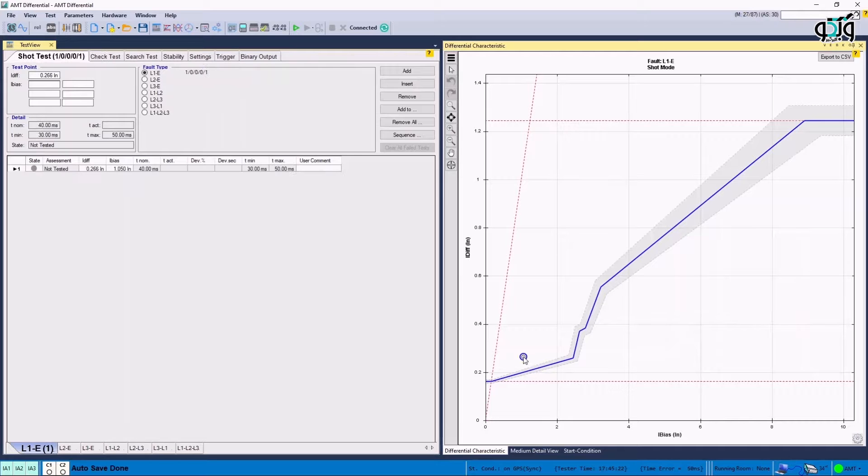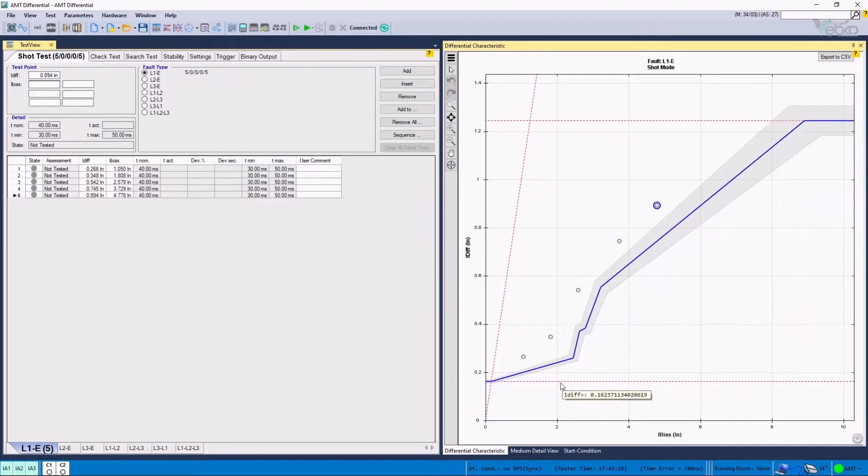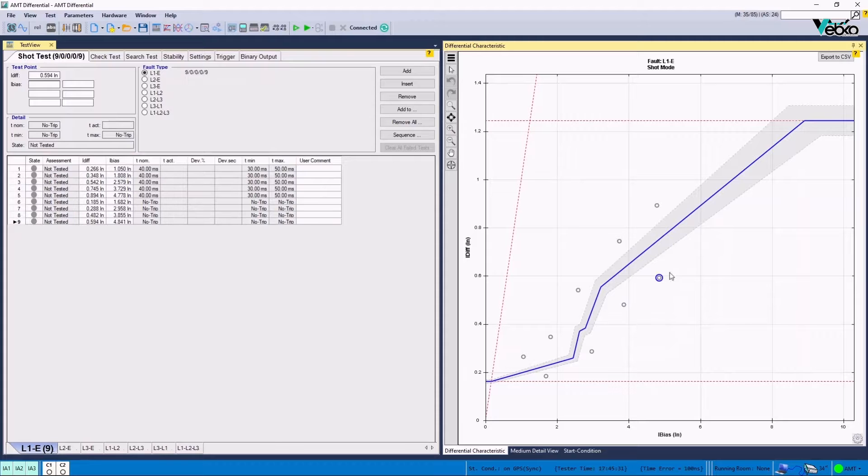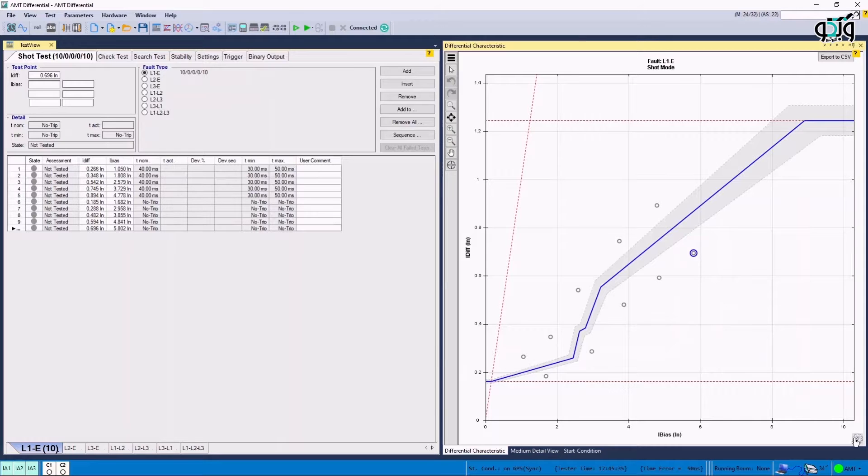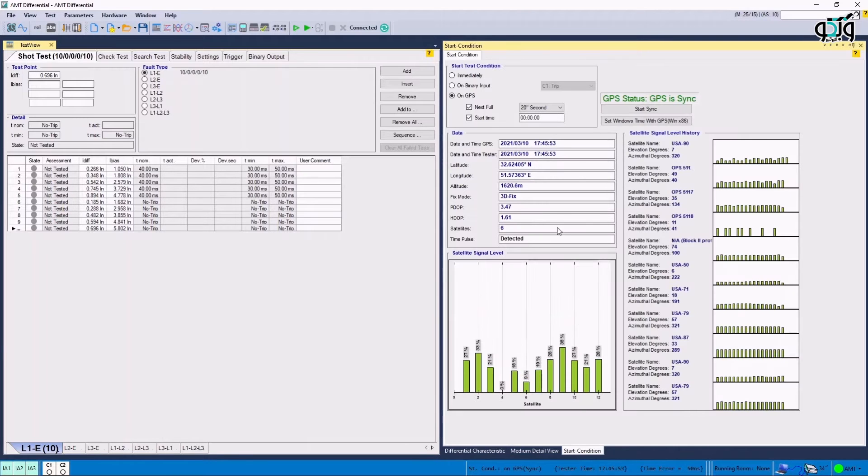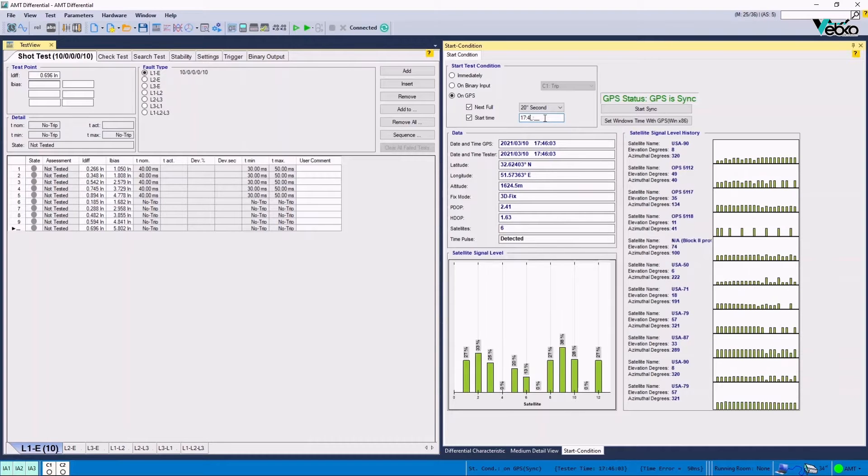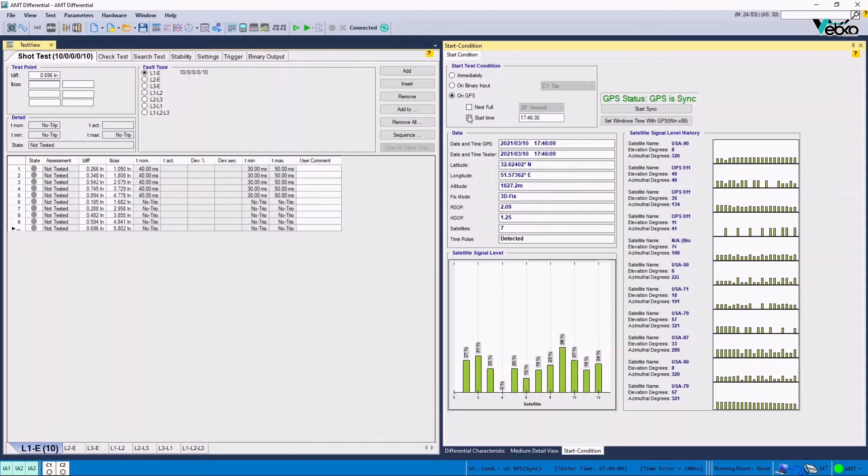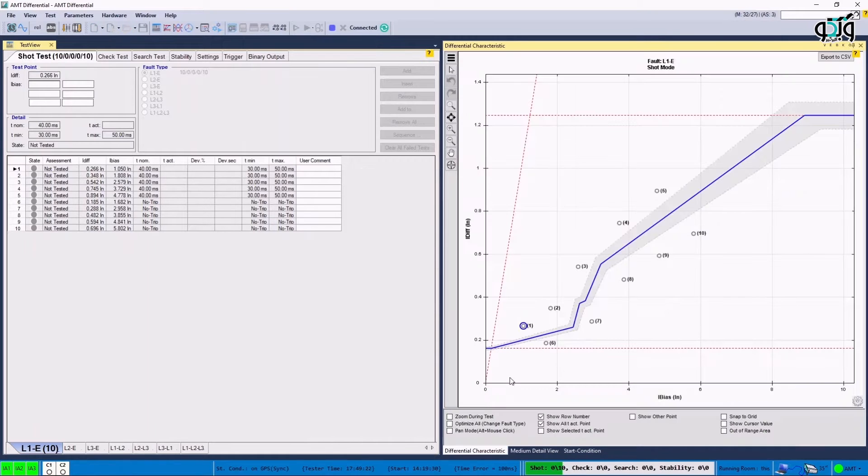In the next step, after coordinating with the opposite side, some points are put on the differential characteristic and after adding them to the test table, it is possible to compare their coordination which is a combination of I bias and I diff to ensure that the conditions are the same. By clicking on the cog icon at the bottom of the differential characteristic window, it is possible to use the features that help users to better supervise the test. Now, by returning to Start Condition tab in On GPS section, a time is considered as the start time after coordination with the opposite side and then by unchecking NextFull option whose function has been explained before the test is initiated.